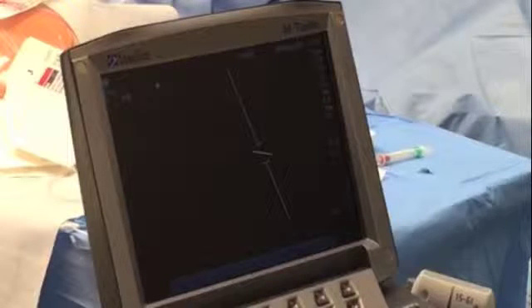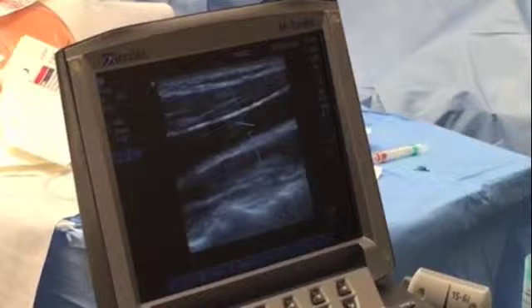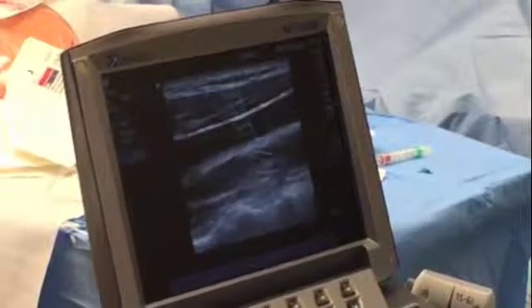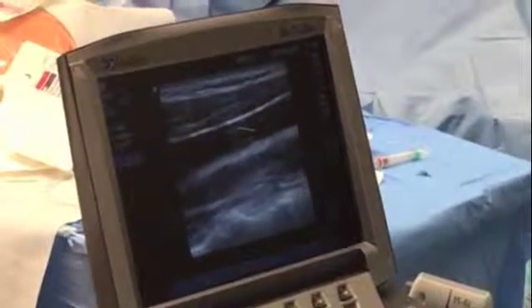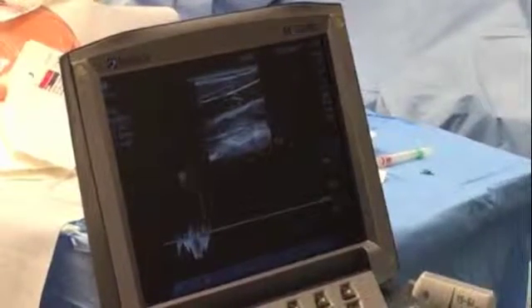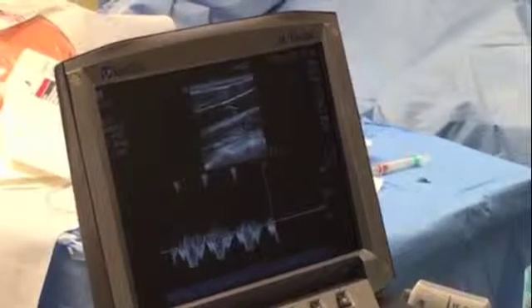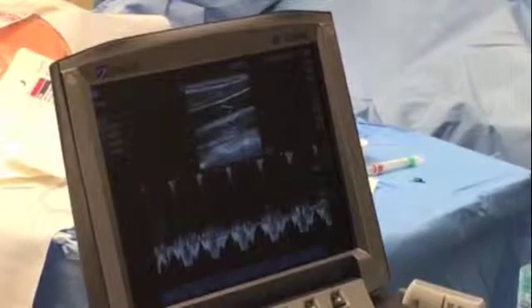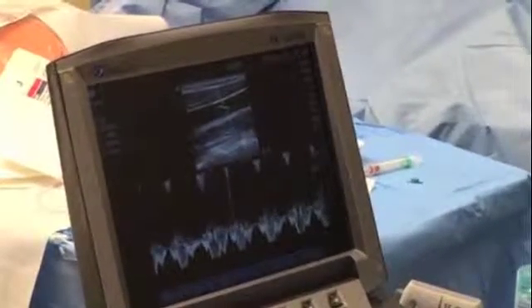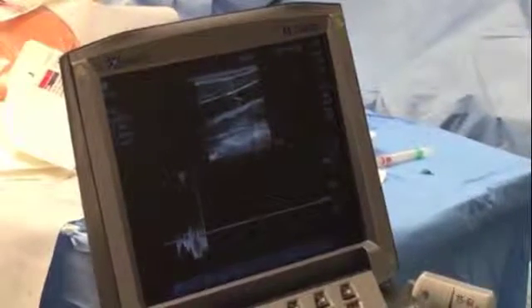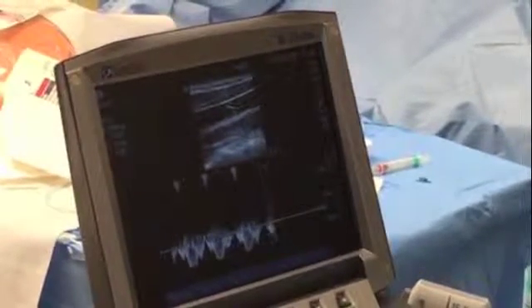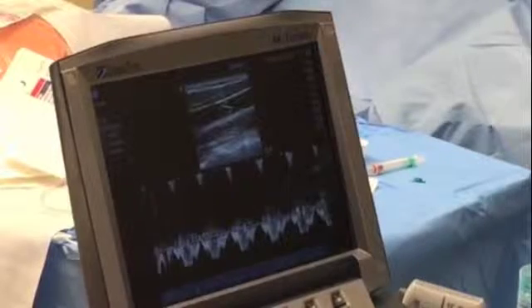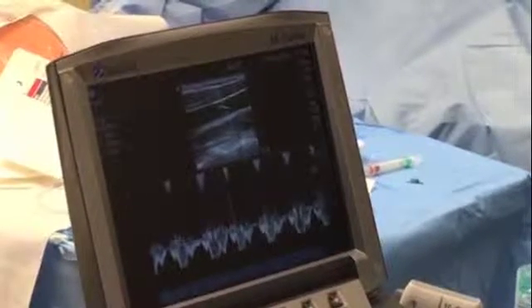In Doppler mode, you will see a long vertical line transected by a short horizontal line in the middle. The long line represents the angle of the ultrasound probe. Press select and using the touchpad, move the short horizontal line into the middle of the vessel. Once your lines are properly positioned, press the Doppler button again to produce the flow signal. This will generate both the audible, pulsatile flow signal of the vessel, as well as the visual wave tracing of the pulsatile flow along the bottom of the screen.